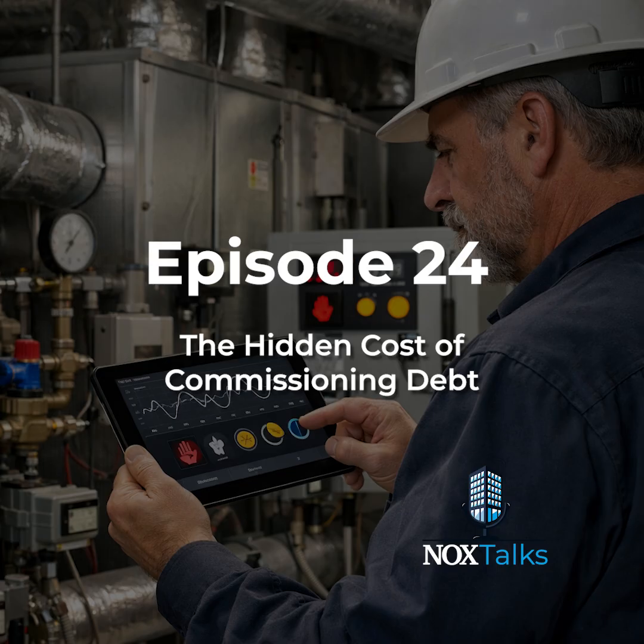Today, we're diving into the hidden cost of commissioning debt. Not technical debt in software. Building debt. The kind that piles up when a site gets handed over. The trend logs look fine at a glance, but the supply air reset is broken, a discharge sensor is lying, a few overrides never got cleared, and the sequence was never really proven in the field.